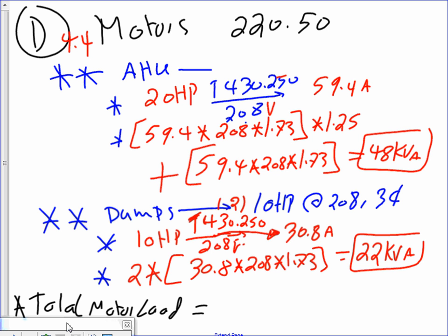All these motors are the same. They're motors. Under this step, you choose the largest out of all the 20s and all the 10s. Did you guys hear me? The largest of all the 20s and all the 10s. And you multiply the largest by 1.25, which we already did here. Do we have to pick the largest here? No. We already picked the largest at the top. Am I making sense? You take the largest of all the motors. And don't forget that I always divide by 1,000 and don't show that, because you guys are smart, you know how to put the key. Okay.